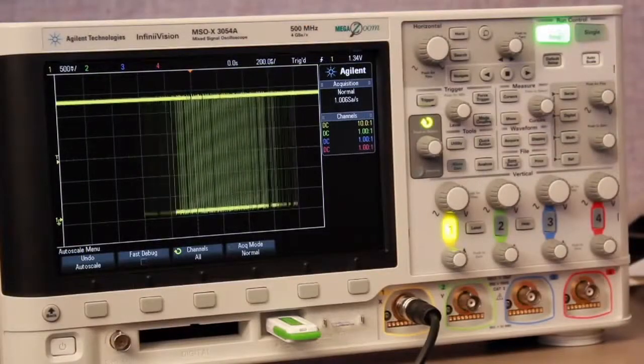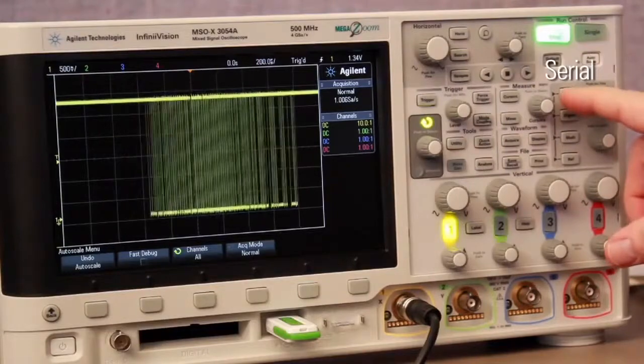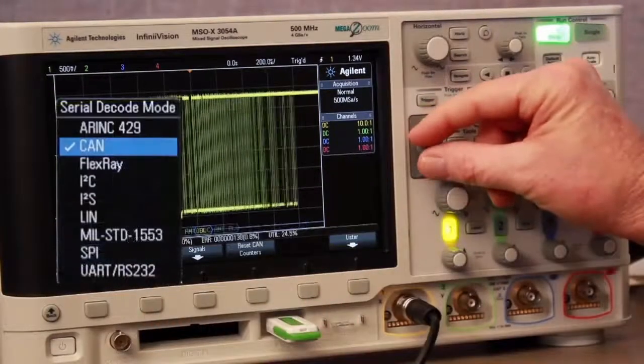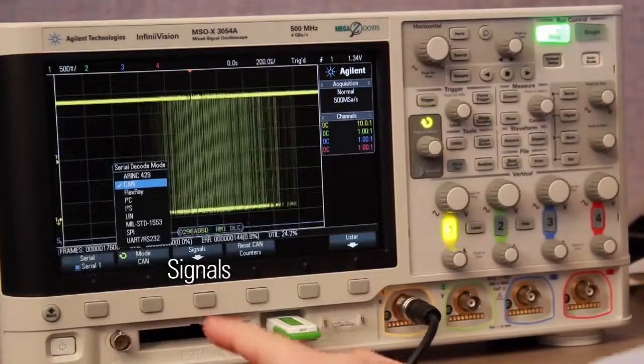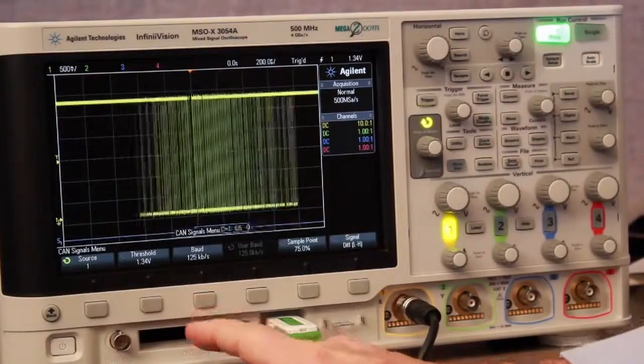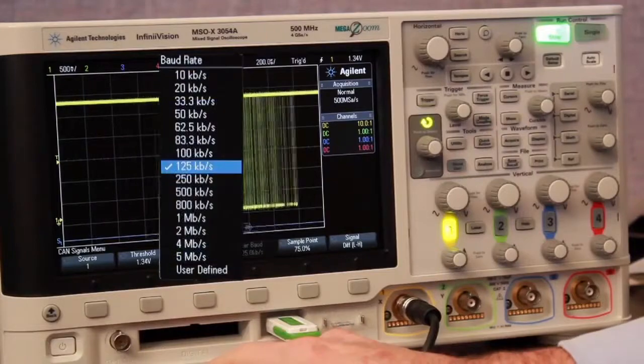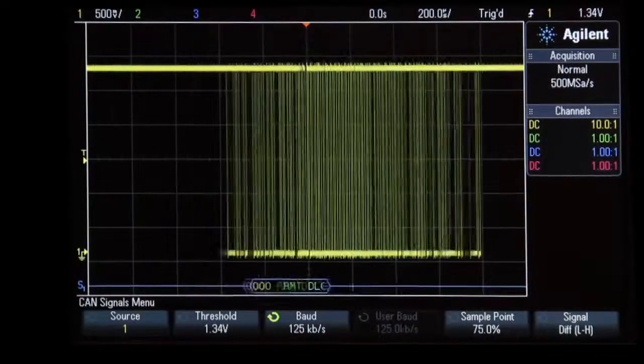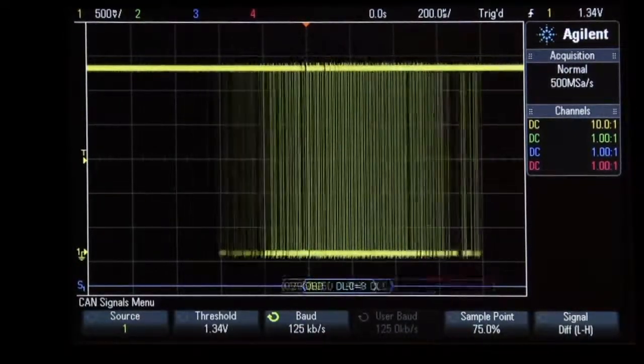To decode this bus, first press the serial front panel key and then select the CAN decode mode. Then press the signal soft key in order to select the appropriate baud rate. The scope is now decoding this bus, but the scope is still just triggering on random rising edges of the signal.